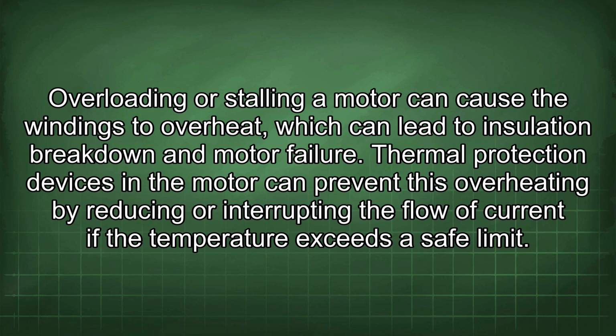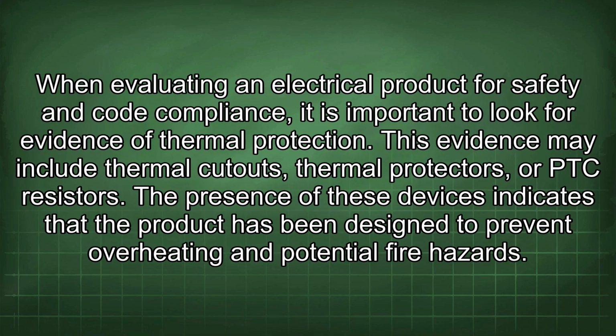Thermal protection devices in the motor can prevent this overheating by reducing or interrupting the flow of current if the temperature exceeds a safe limit. When evaluating an electrical product for safety and code compliance, it is important to look for evidence of thermal protection. This evidence may include thermal cutouts, thermal protectors, or PTC resistors. The presence of these devices indicates that the product has been designed to prevent overheating and potential fire hazards.